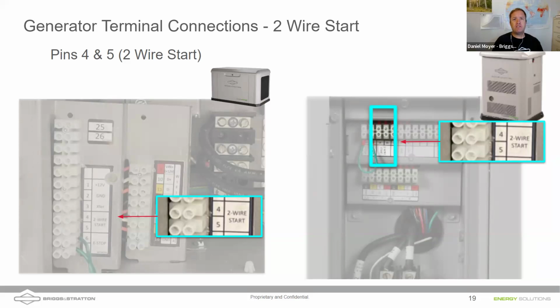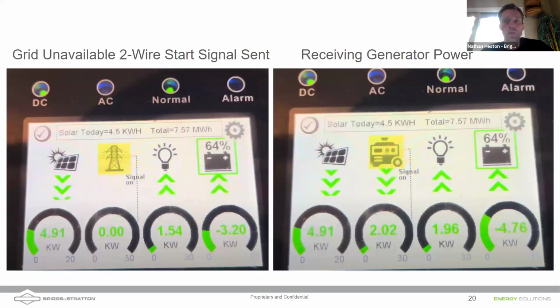Yeah, and I believe a lot of the Kohlers are normally open for that two-wire signal to start. Some of the other brands may not be normally open, but there are little adapter kits that can be leveraged. You can go from normally open to normally closed through a relay adapter. What Daniel's pointing out is that the two-wire signal to start on the Solarc 15K is the standard normally open circuitry, and that's what we employ on Briggs and Stratton generators. There might be some generators with a two-wire start which is a normally closed circuit, but you would need to add an adapter.